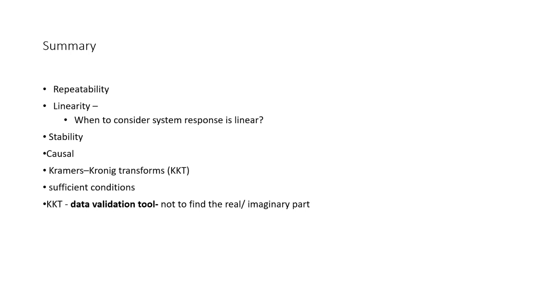The next week we saw how the instrument is behaving. In fact, how we take it in potentiostatic mode or galvanostatic mode, and whether it is a single sine or a multi-sine input. How is the equipment giving the sine input, and what is happening. What we are giving is something which is a function of time as the input. That is, potential or current as a function of time, that is E_AC equal to E_AC naught sine omega t. That is what our input is, either in a single sine format or a multi-sine format.